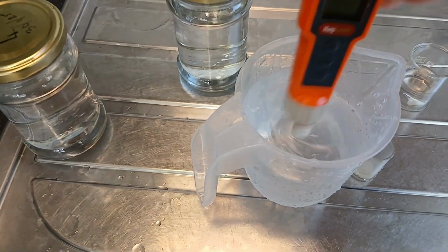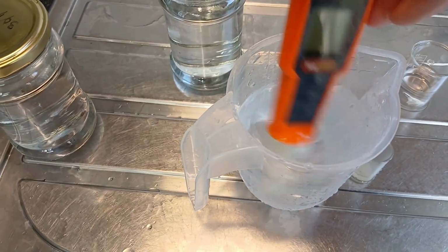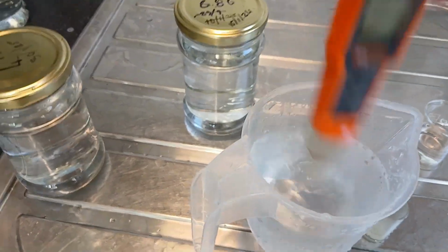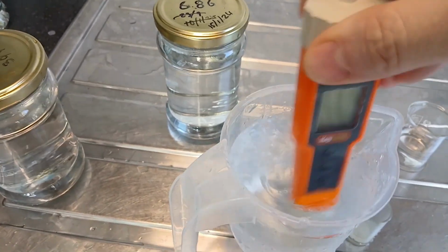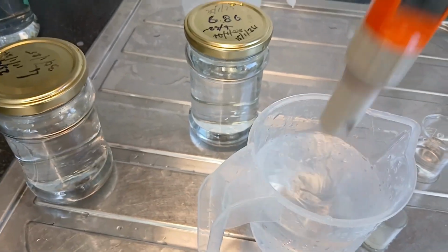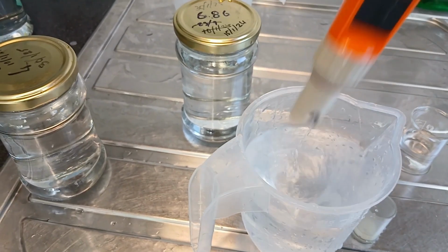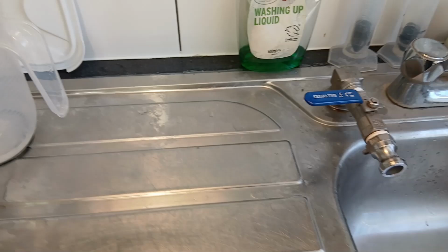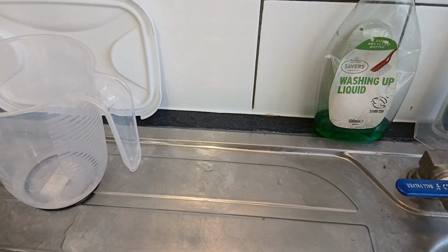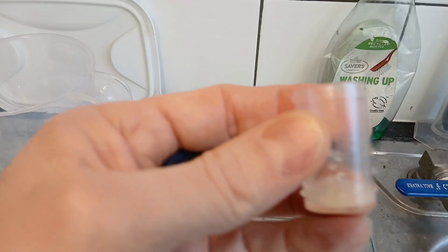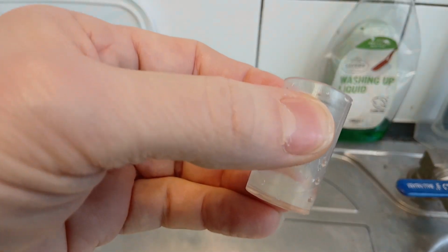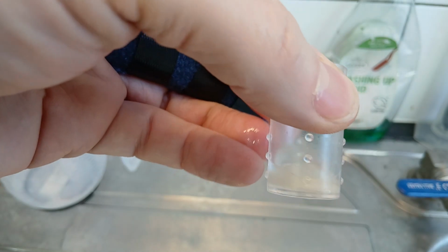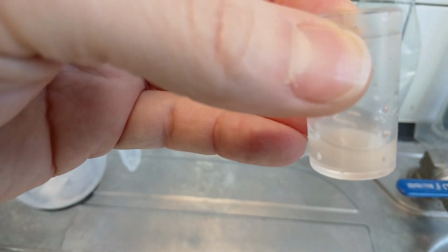So after the calibration's finished, I'm just cleaning it, removing all that buffer solution with the meter off, with some RO water, heavily diluting it hopefully, removing it from the probe. So that's safe to store. So once that's rinsed off, stabilize the camera. We've got the storage tube. Now you can see there's a little bit of the electrolyte solution in the bottom of there. It's maybe enough.